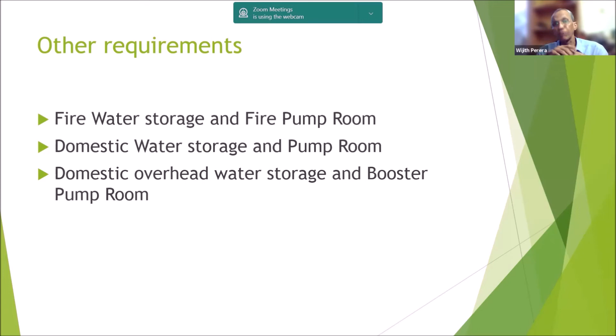Then all these need to be planned in consultation with the structural engineer. That will facilitate a well-coordinated building with functional services and access for maintenance. Why I'm repeating these is that the locations of all those facilities I mentioned are pretty flexible, other than the main incoming water sump, which has to be at ground level. All the others can be located in any part of the building, depending on where it is most convenient for the rest of the design. It can be on the roof. This entire fire water sump, domestic water sump, fire pump room, domestic pump room can all be on the rooftop, but that has to be coordinated at the beginning.